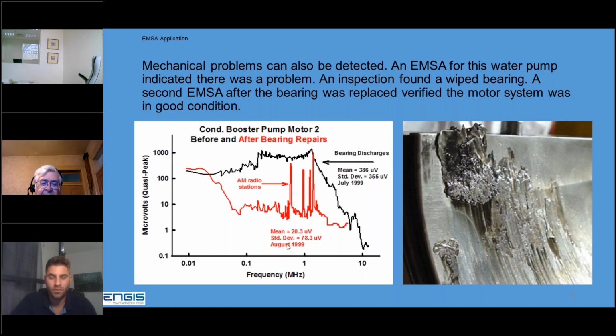Then we went back down the next month. This is what they saw. I would assume this very severe bearing wipe happened during shutdown. I can't believe it was running that bad. The bearing would have overheated. So they had a minor rub, and then that got much worse when they took that motor out of service. But anyway, they changed out the bearing.